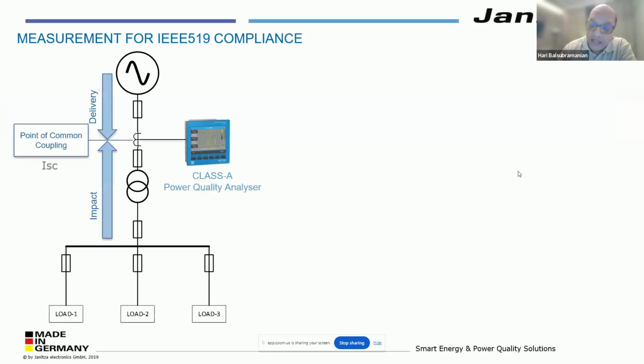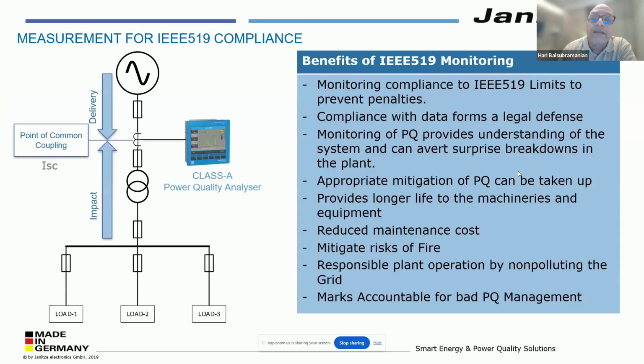For example, as I said here, the class A device needs to be at the point of common coupling. And by doing this, we are making the grid stronger. In other words, when we comply with IEEE 519, we are making the grids stronger. When the grids become stronger, we don't have problems of voltage issues. We don't have breakdowns in our plants. We have a longer life of our equipment and machinery, and we mitigate the risk of fire due to harmonics in our system. So there are quite a lot of benefits of following standards like IEEE 519, and thereby we make our life much easier in running an operation.